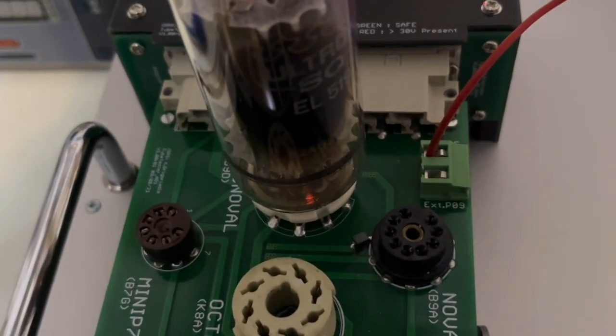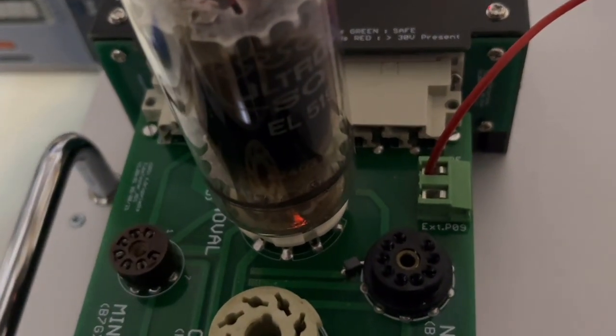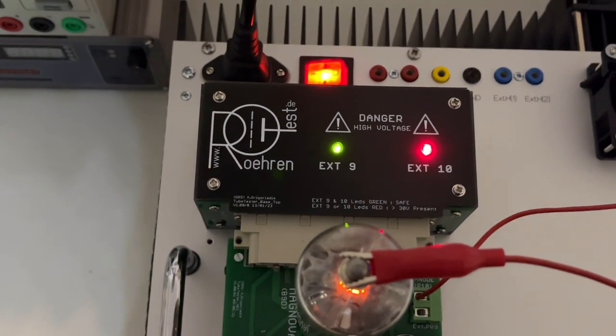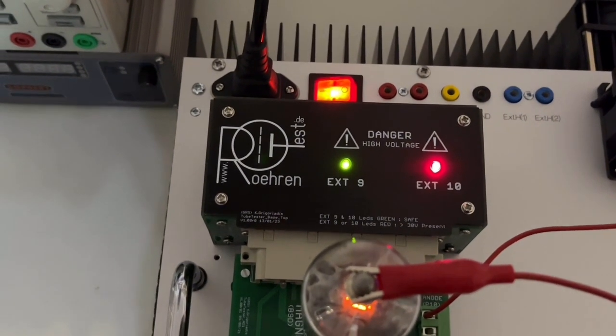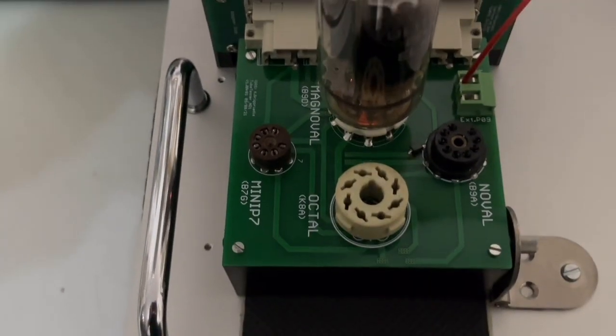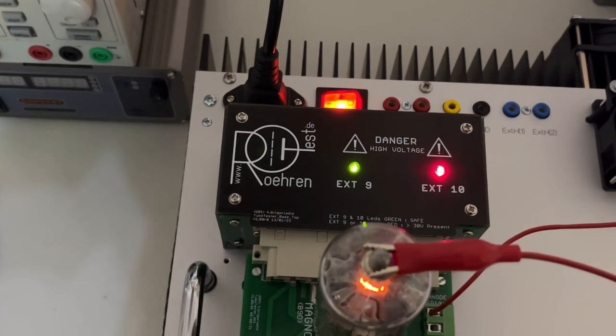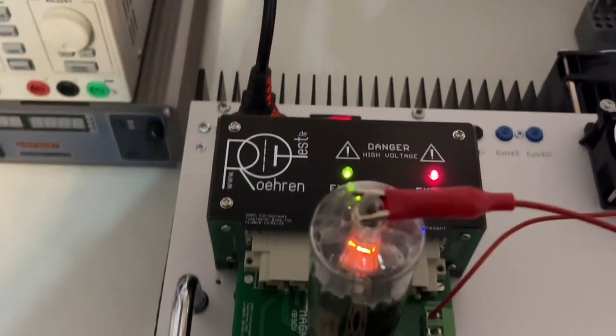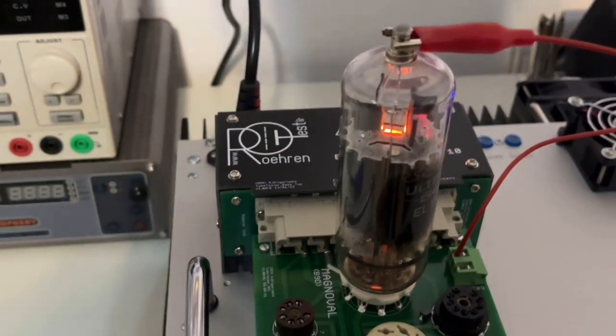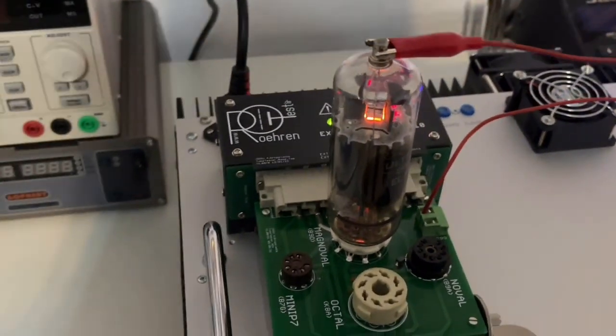And of course this connector here - this is why I made it - because I want to know if I really still have a higher voltage on the connectors or on the socket themselves, and not just rely on what the program tells me about the relays being on or off. It's getting warmer - look at that, isn't that beautiful? That's for the Halloween season.